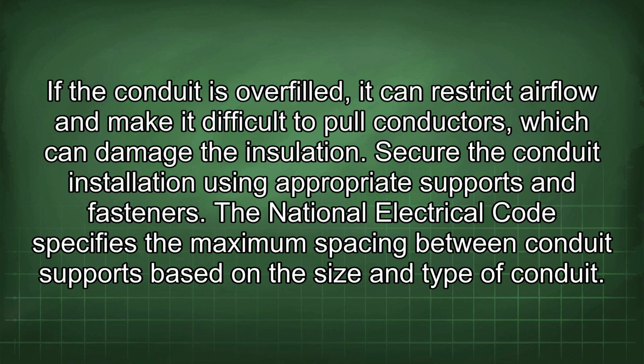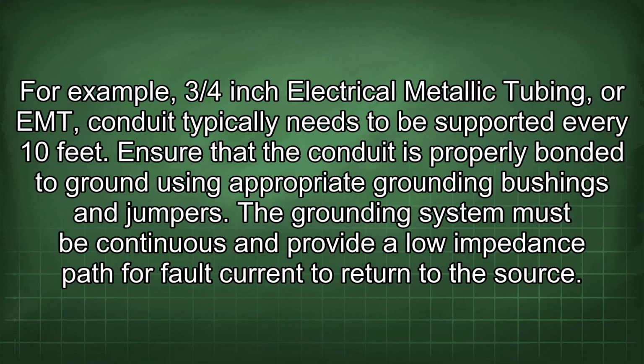Secure the conduit installation using appropriate supports and fasteners. The National Electrical Code specifies the maximum spacing between conduit supports based on the size and type of conduit. For example, 3/4-inch electrical metallic tubing, or EMT, conduit typically needs to be supported every 10 feet.